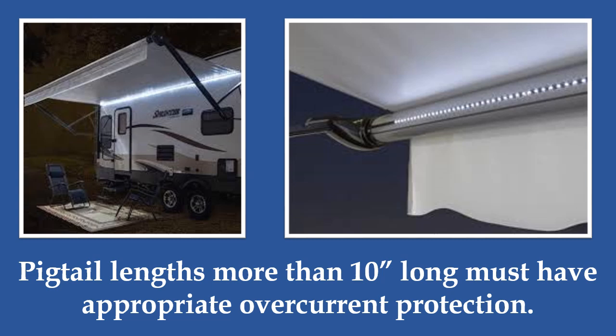These long, thin gauge pigtails could be and have been in the past attached to 14 gauge wire on 15 amp fuses that supply power to the awning motors. The 15 amp fuse or breaker for the motor is way too large over current protection for these small gauge awning light wires. These small diameter conductors require overcurrent protection of only 6 amps or less. 15 amp fuses will not protect the wire unless the pigtails have been reduced to less than 10 inches in length.